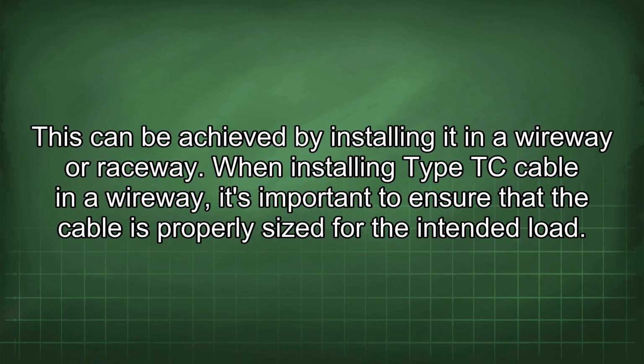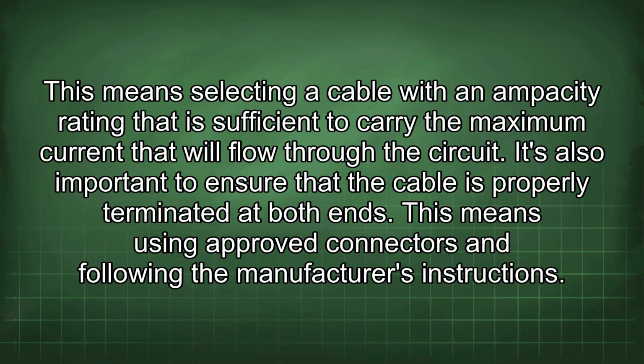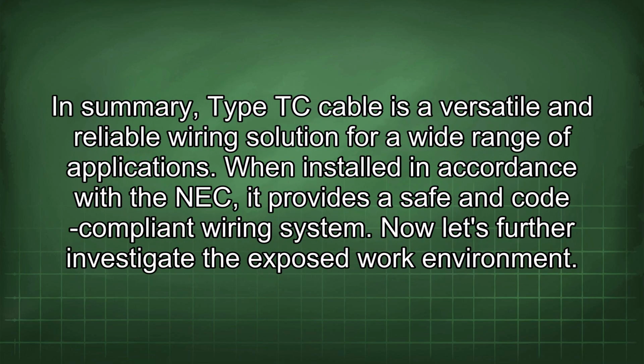When installing Type TC cable in a wireway, it's important to ensure that the cable is properly sized for the intended load. This means selecting a cable with an ampacity rating that is sufficient to carry the maximum current that will flow through the circuit. It's also important to ensure that the cable is properly terminated at both ends. This means using approved connectors and following the manufacturer's instructions. In summary, Type TC cable is a versatile and reliable wiring solution for a wide range of applications. When installed in accordance with the NEC, it provides a safe and code-compliant wiring system.